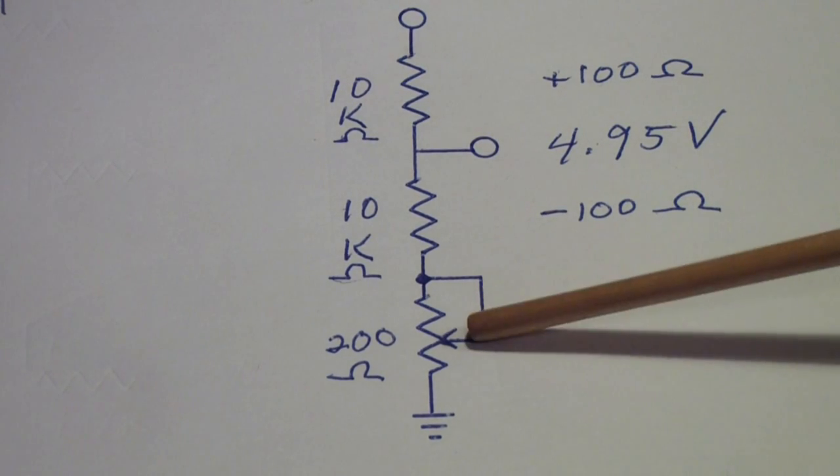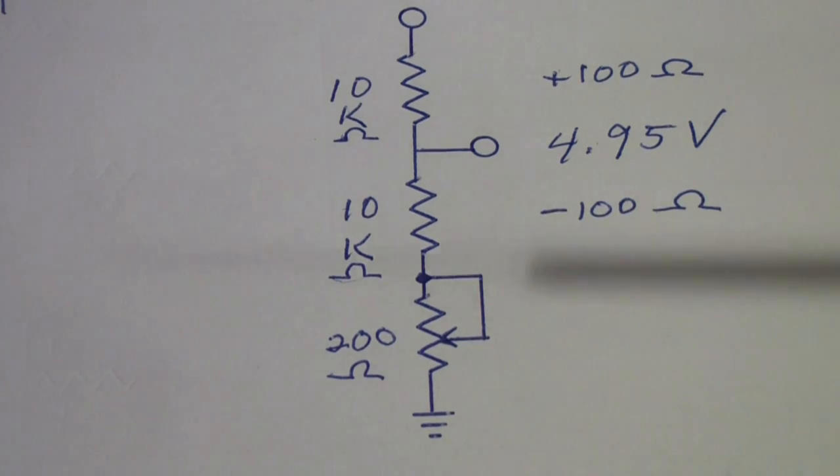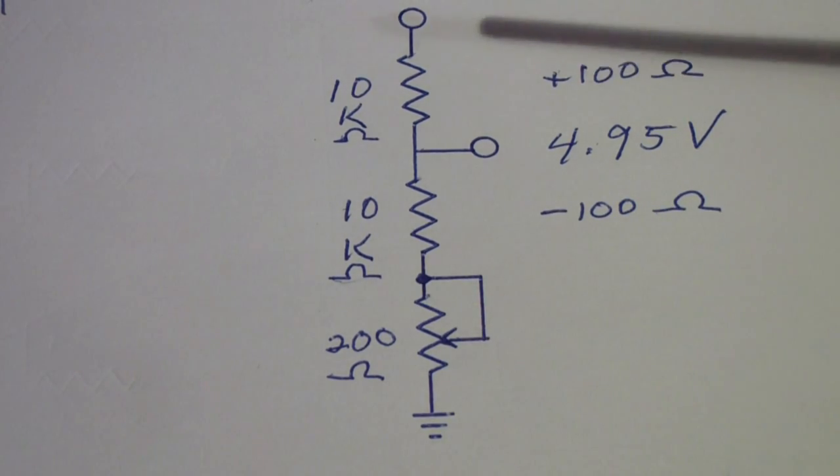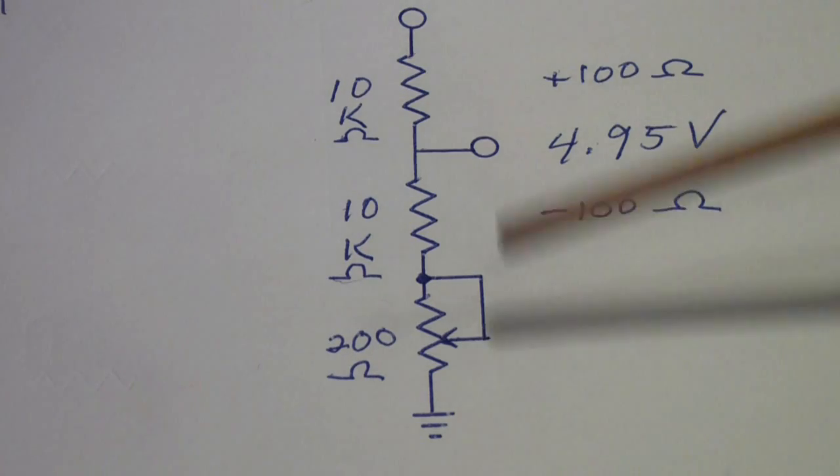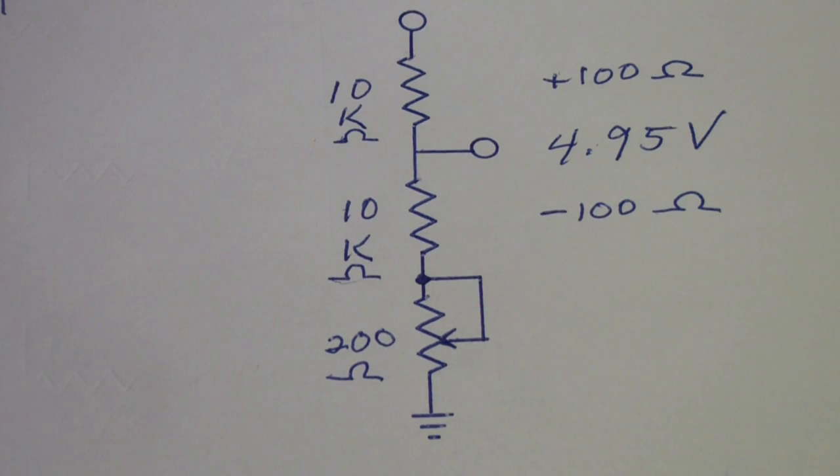This was necessary not just for kit scopes like the Heathkit, but also for factory manufactured scopes, because, among other things, over time, resistor values would drift. So, let's look at a little bit at that and how that might go about being calibrated.